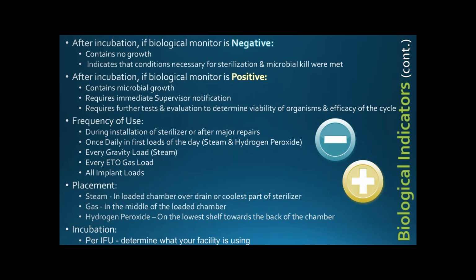They also use these for our Sterrad or our hydrogen peroxide gas and things like that. To answer your question, in my opinion, unless you have run the full cycle, I would not release anything, because there's multiple different steps and phases that you need to have. So if you abort your cycle, even if your chemical indicator has passed, I would not feel comfortable releasing that instrument set.